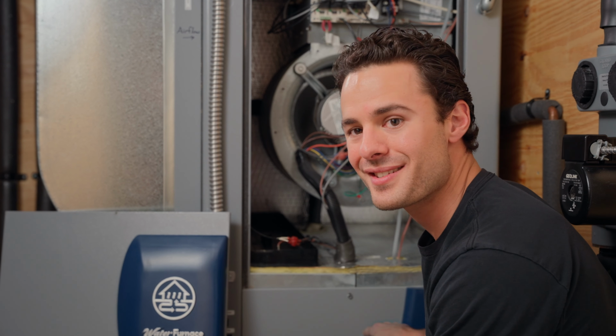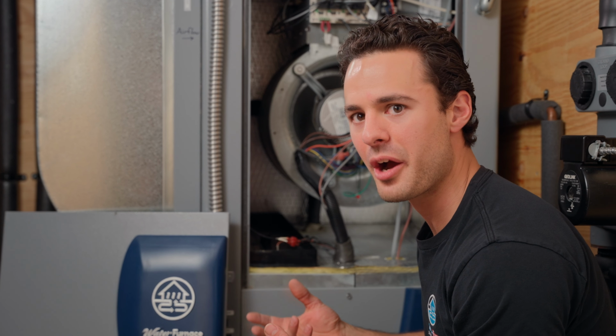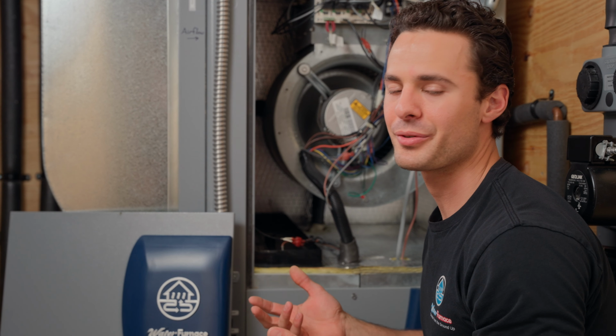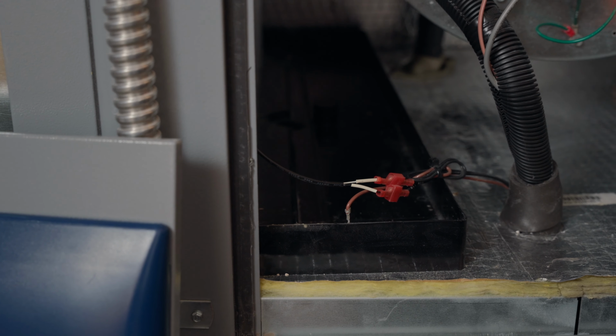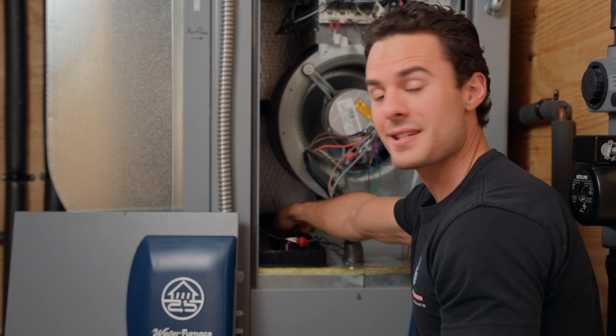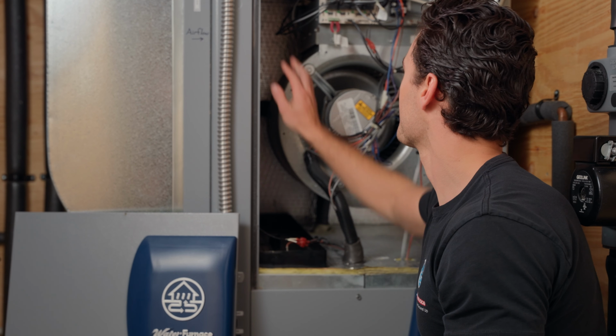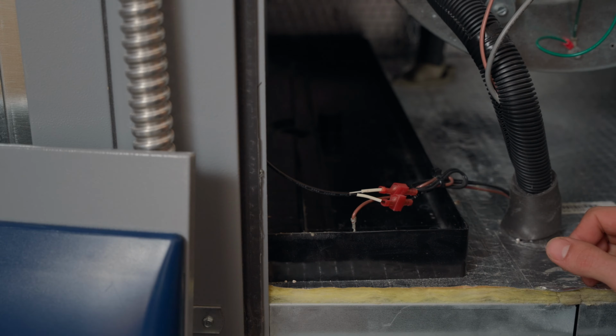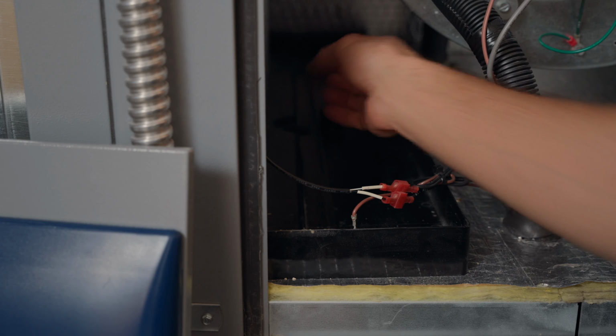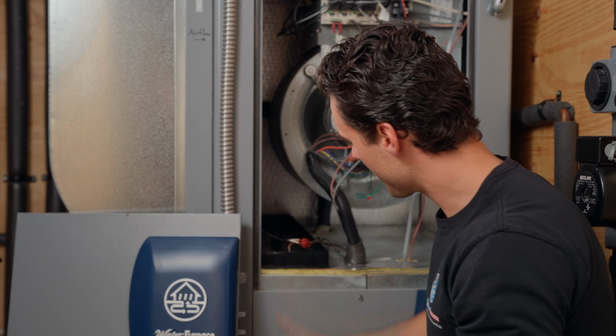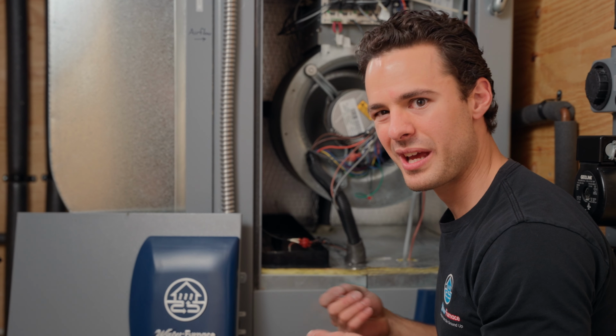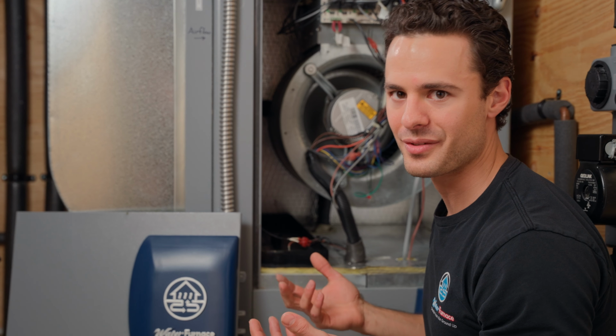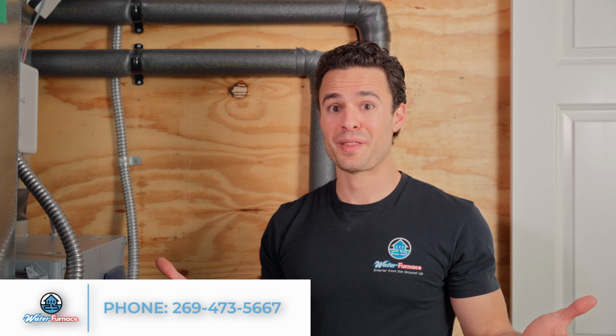As water sits in that trap over time, it can kind of gum up and eventually maybe create a clog. So in order to prevent that, you can either put some chlorine tablets in this tray, or when you're done with the air conditioning season, go ahead and just dump a cup of Clorox bleach in that, and it'll go down and sit into that trap and just eat away any of that debris that may collect over time. So that's pretty much it for the maintenance.